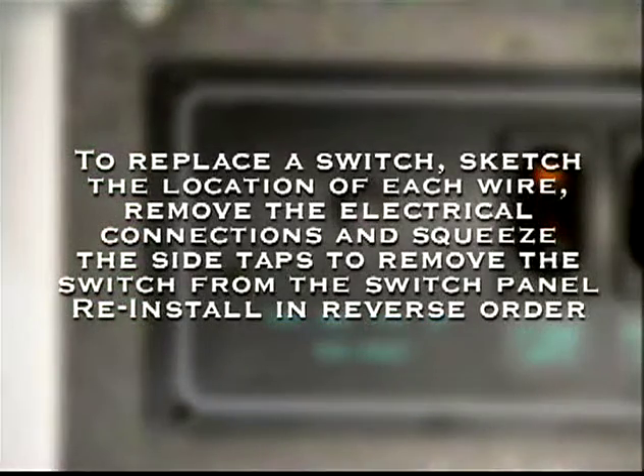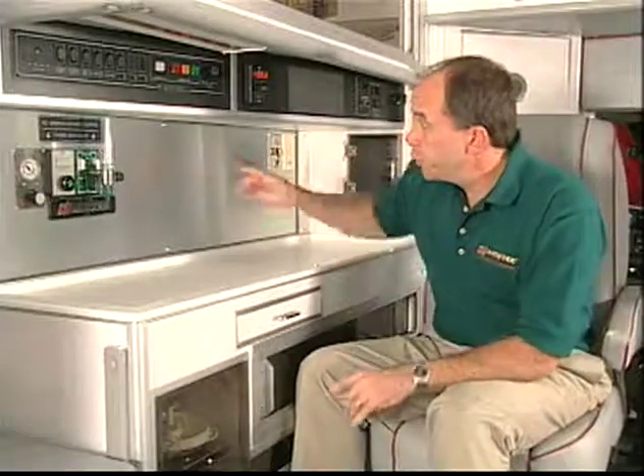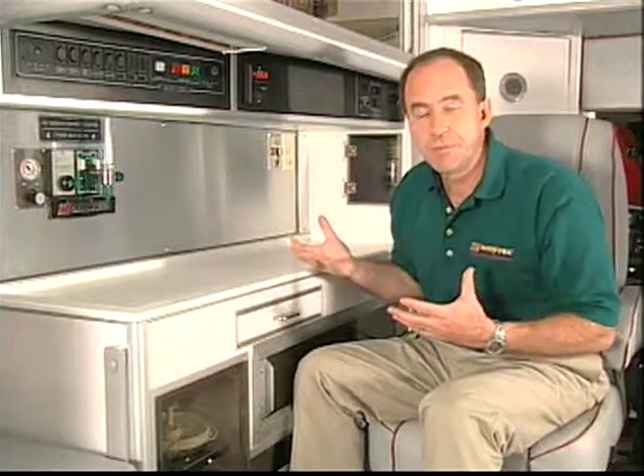Removing the screws securing the rear electrical switch panel provides access to the electrical switches. To replace a switch, sketch the location of each electrical wire. Remove the electrical connections and squeeze the side taps to remove the switch from the switch panel, and reinstall in the reverse order. Removing the screws securing the action area wall provides access to any attached equipment, such as oxygen outlets, vacuum outlets, 115-volt AC outlets, 12-volt DC outlets, as well as any other equipment you specify.